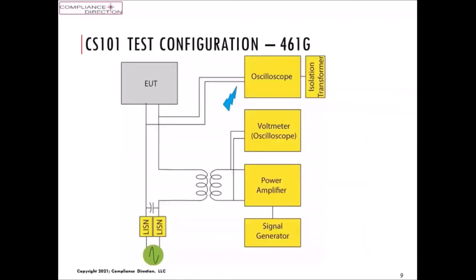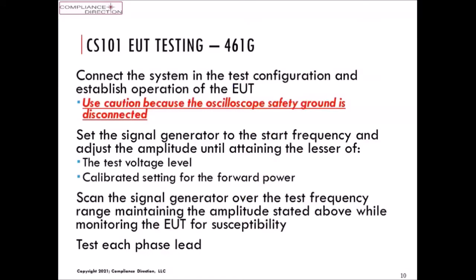Now, when it comes time to do the test, the current version shows that we're measuring the test voltage at the EUT terminals, what we're applying to the circuit. And the current path takes us from the coupling transformer into the EUT, all the way back around through the LISNs, the power source, back to the other side of the coupling transformer on the secondary. With that, there'll be feedback across to the power amplifier, and we'll see some of that in the voltmeter settings and how it affects the power amplifier performance. And basically, that's what these words are saying. Remember, we disconnect the safety ground so the oscilloscope terminals become live. So be cautious, especially if you're doing three-phase power, where you connect to one of the phase leads as the alternate line. So the idea is to test each phase lead.